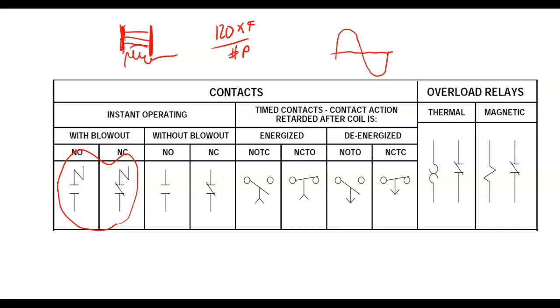So you can buy a DC drive and a DC motor, or you can buy an AC drive and an AC motor, and AC motors are very, very cheap per horsepower. Once they figured out how to control the voltage and frequency, AC motors started dominating speed control. If you get into some old applications, you'll find DC drives, but newer applications are probably going to be all AC motors because of the price of the motor.